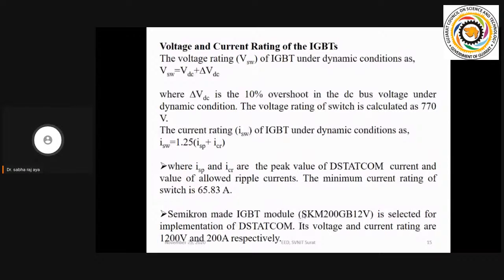And again, how can we decide the current rating of the switch? I_switch you can get based on 1.25 (I_sp + I_CRPP). That means the peak value of the supply current, you can say the peak value of the STATCOM current, plus the value of the allowed ripple current. Here in practical purpose, we have taken a 1200 volt, 200 ampere IGBT, because we will not get 70 or 80 ampere. So maybe you can take somewhat higher side.